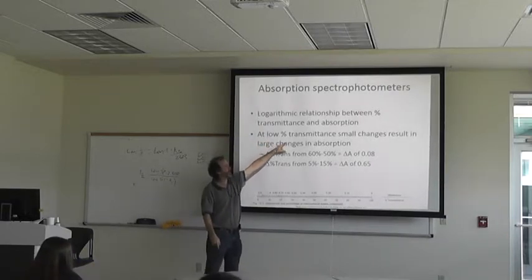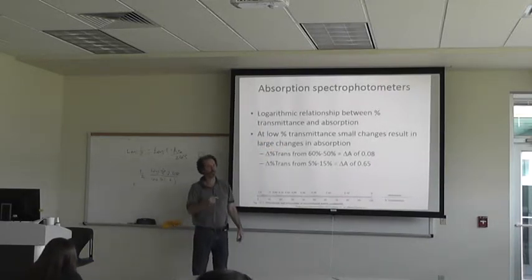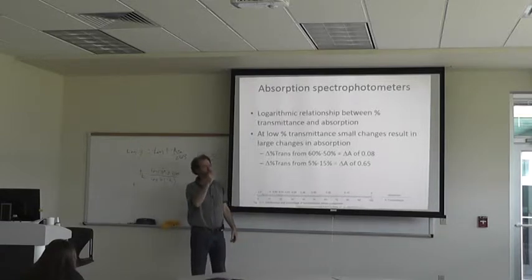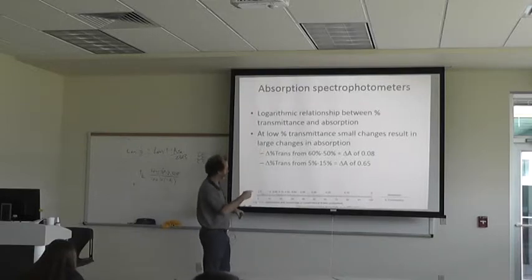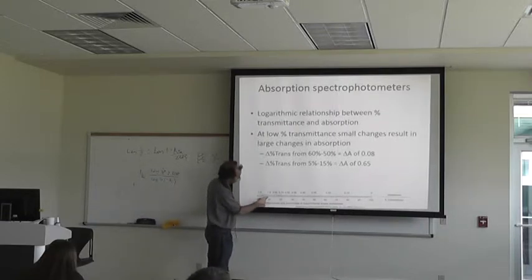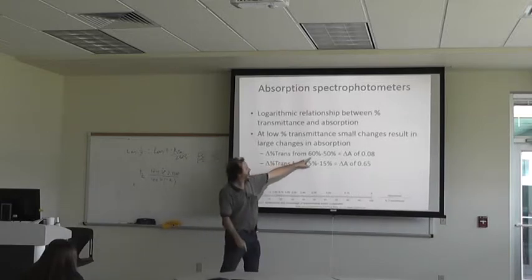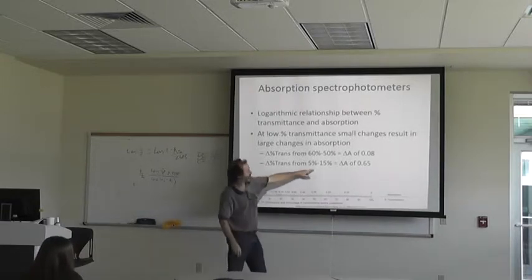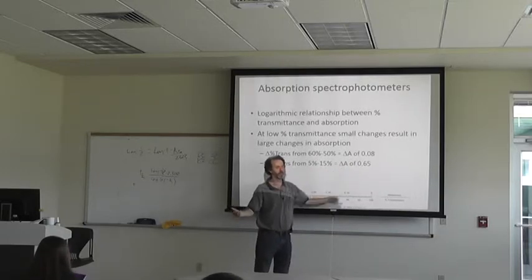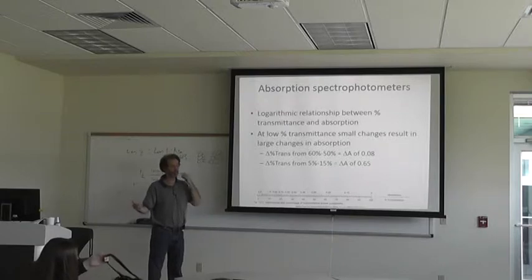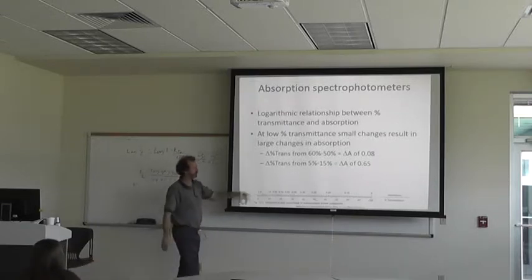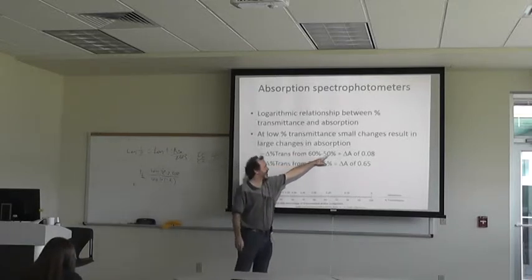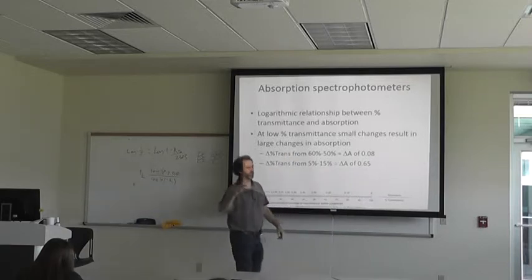At low percent transmittance, small changes will result in large changes in absorbance. Those machines have variability built in — noise in the machine. So any variability, if you have low percent transmittance, it's absorbing a lot — really high absorbance. If you go from 5% to 15% transmittance, the change in absorbance is 0.65. That's almost one whole absorbance unit — a huge change in your measured concentration, and that could just be 10% noise. Versus 60% to 50%, you get a change in absorbance of only 0.08 — a much more negligible change.